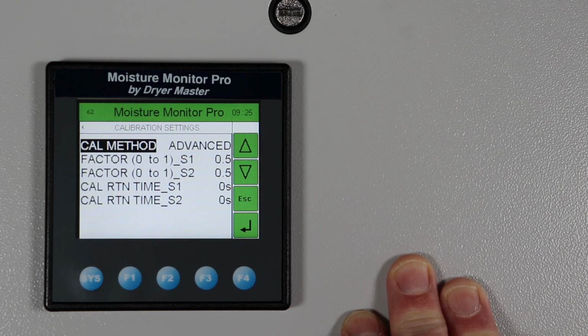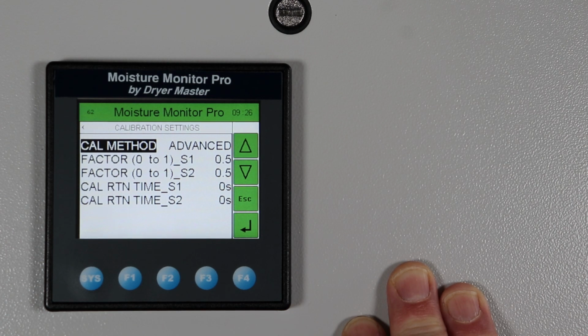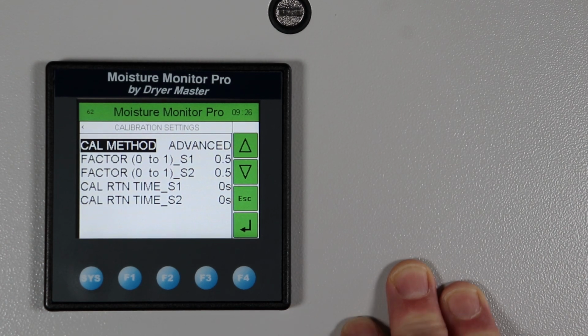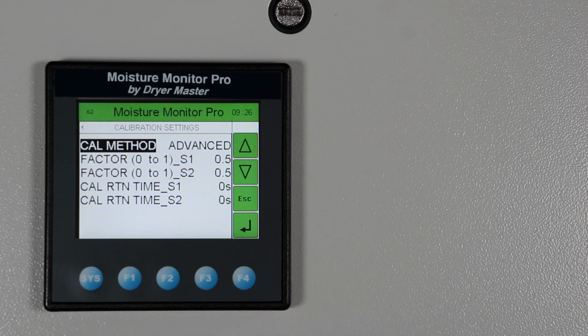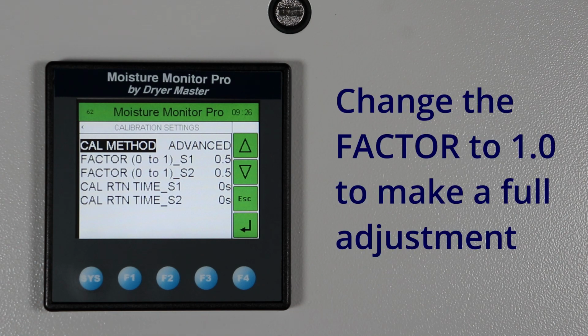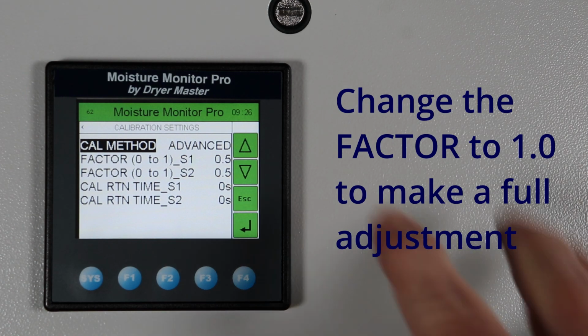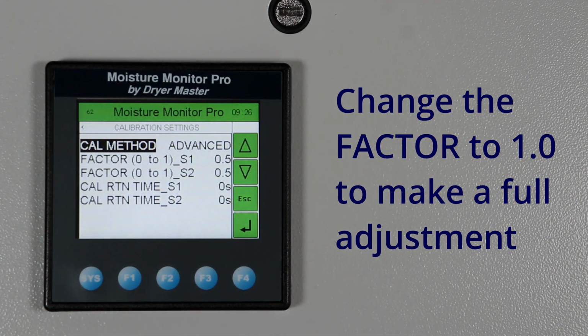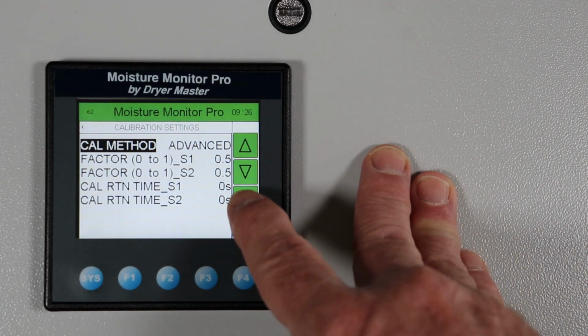And the reason for that is there's always variation even when you're doing a manual sample. So let's say you take enough product for running 3 tests on a sample. The chances of all 3 tests from that sample being the same are pretty low. There's going to be a range of values. So to avoid making too much of an adjustment at one time, what we recommend is making half of the adjustment. And so that's what the 0.5 is. If you want to make 3/4 of the adjustment, you can change that factor to 0.75. So whatever you want to do, you can change it there. The default is 0.5, but we'll go through an example.